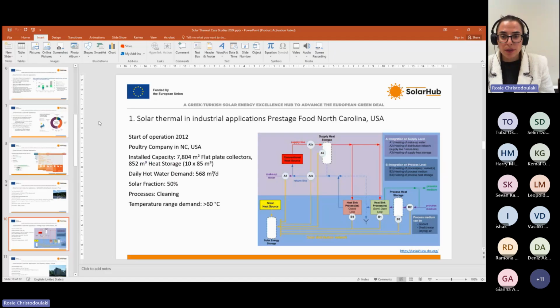Now, the second industrial application that we would like to show you is Prestage Foods in North Carolina in the United States. It started operation in 2012. It is actually a poultry company, so it processes meat, chicken, and the installed capacity is 7,800 square meters of flat plate collectors, with a large heat storage of 10 tanks of 85 cubic meters each. The daily hot water demand of the industry is approximately 570 cubic meters per day, and the solar fraction of the system is 50%.